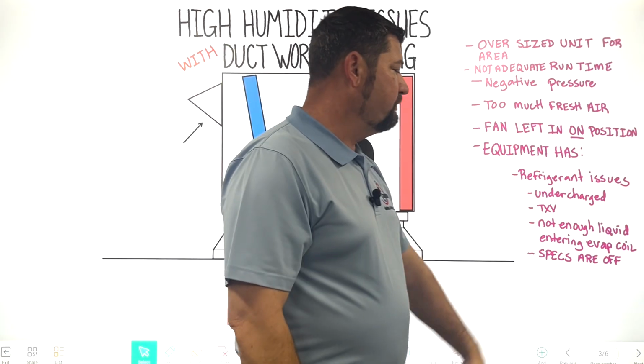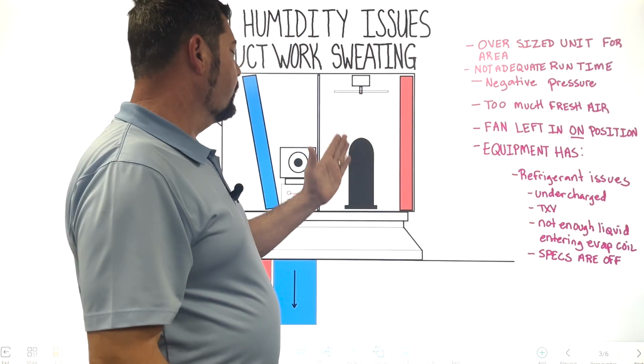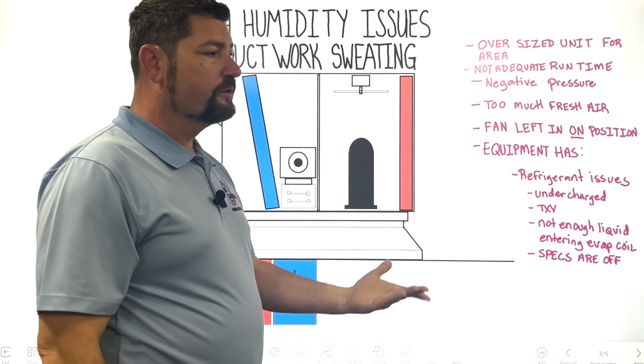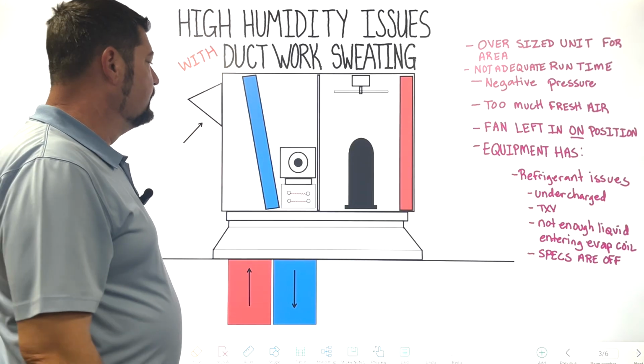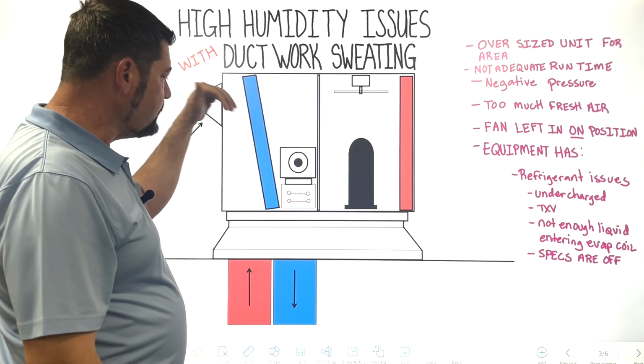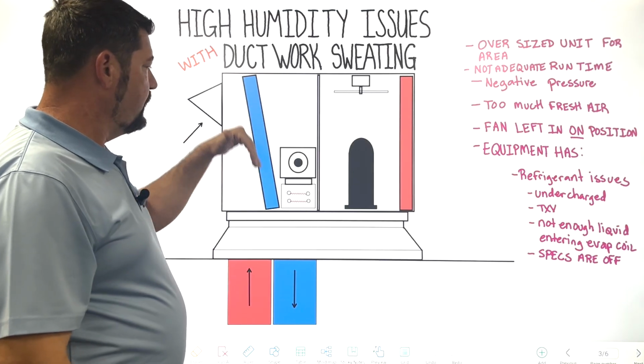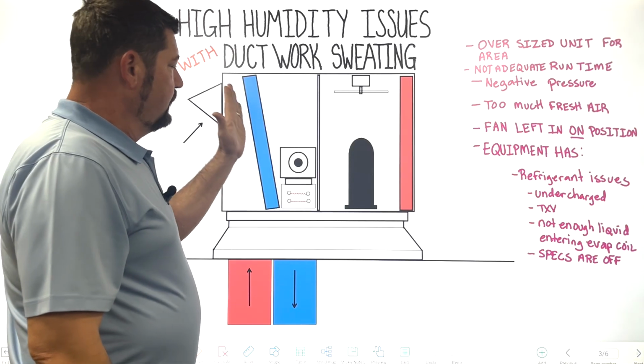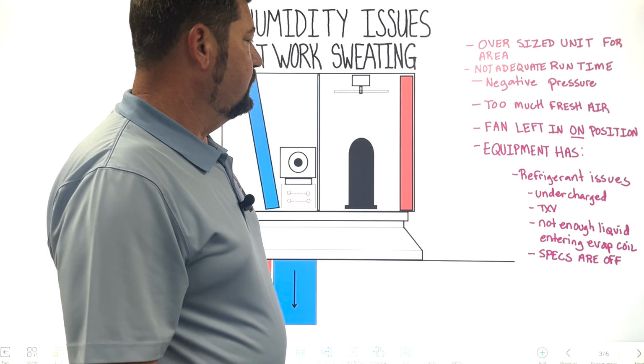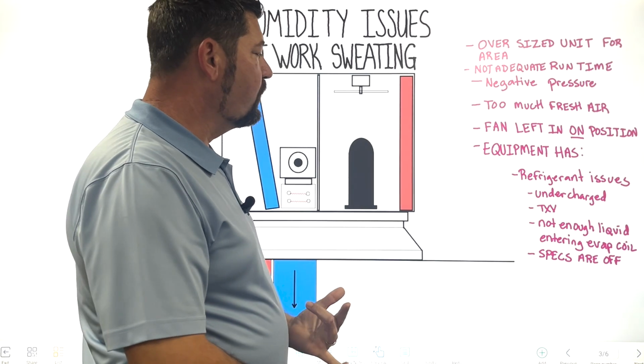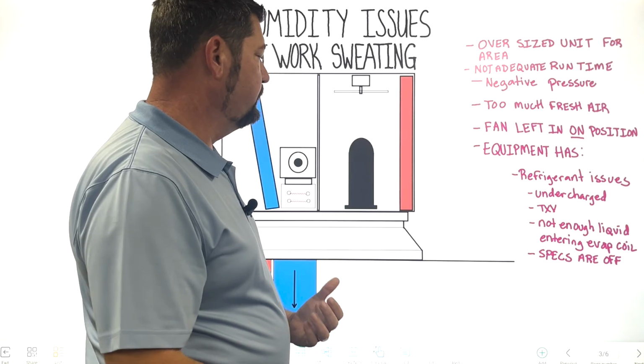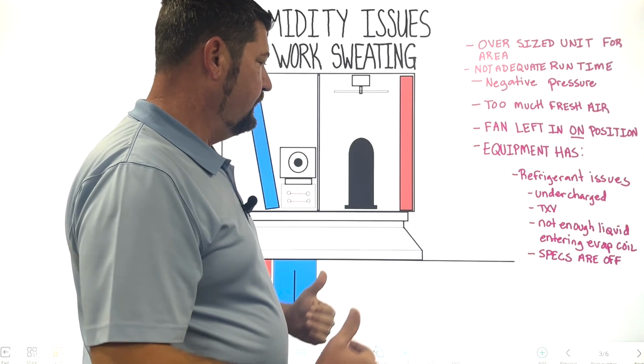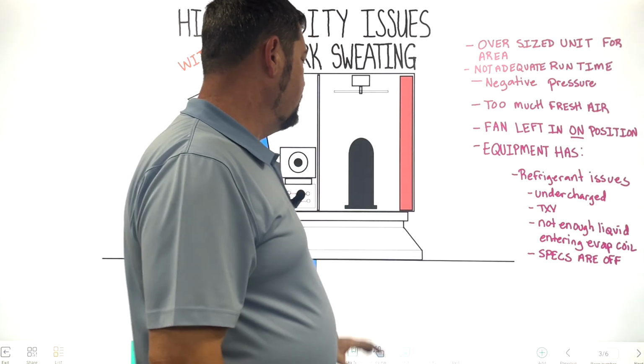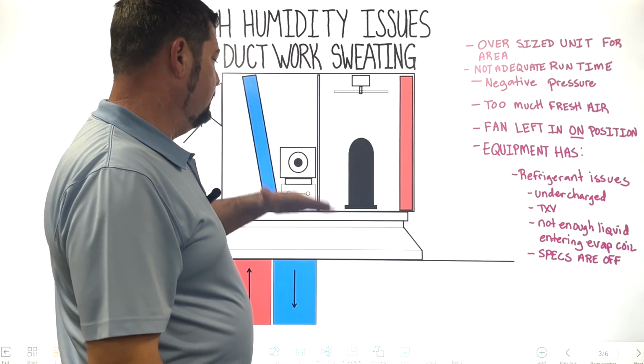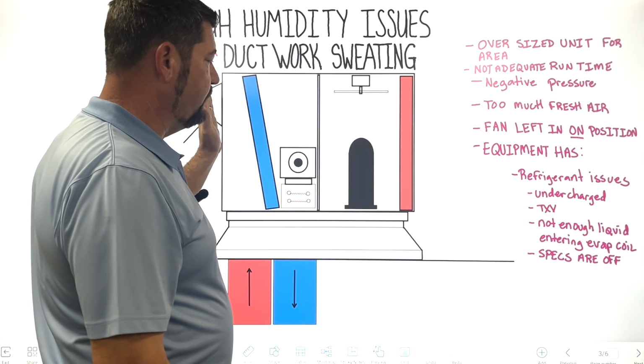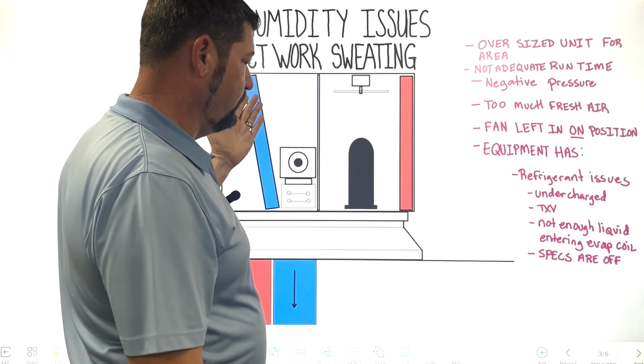The equipment also has many things that could relate to a high humidity. If we're having refrigeration issues, if the system is not charged properly, we can't get the temperature down on the evaporator coil enough to condensate that humidity coming into it via the return duct or the fresh air, in combination of both, then we're going to have humidity issues. So if the system's undercharged, if the system's been worked on and it's no longer at its factory specs and somebody did not add enough refrigerant to it, maybe they charged it and it had dirty filters and they stopped ahead of time, but then the filters were changed out later on. We see that a lot, and it just needed a little bit more refrigerant, but nobody put it in there.